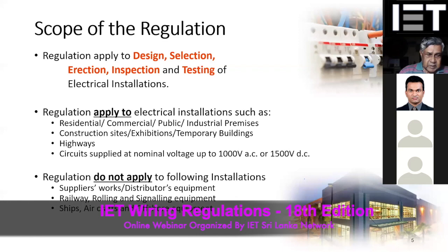Those are separate, and are not covered by the IET wiring regulation. Also railway rolling or signaling equipment, ships and aircraft: even though their voltages are low voltages, you cannot apply this regulation to those types of things, where they have their own separate standards. So we cannot apply this one, even though their voltages are below 1000 volts AC or 1500 volts DC. We cannot apply the IET wiring regulation for these types of locations.